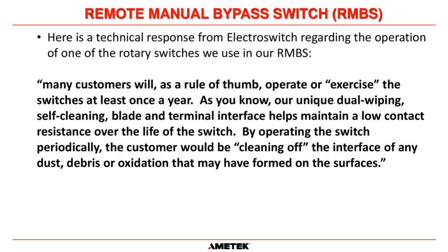So basically, the manufacturer is saying it's good to move your bypass switch on a regular basis, and once a year is okay for that because it does clean the contacts. The last thing that you want is to have a bypass switch, say in a relatively industrial corrosive environment where there's maybe H2S in the air, and you don't move that switch for 10 years, and then you have an instance where the UPS has failed to static bypass, and you want to do some work to get that UPS back up and running, but you have to put the system in remote maintenance bypass.